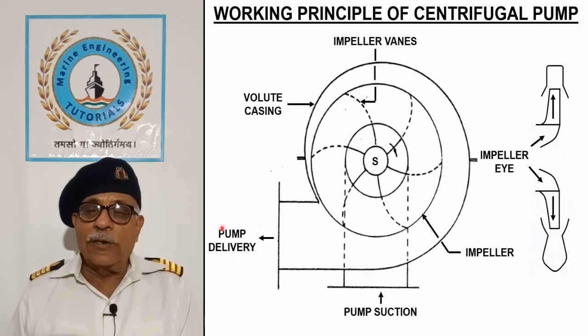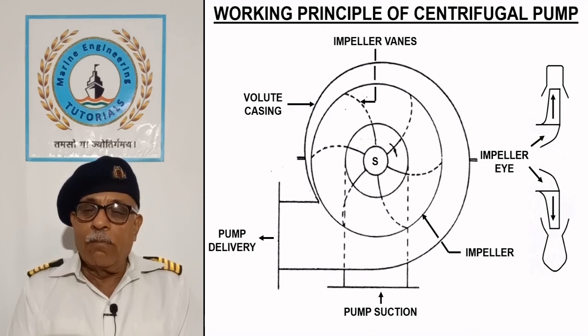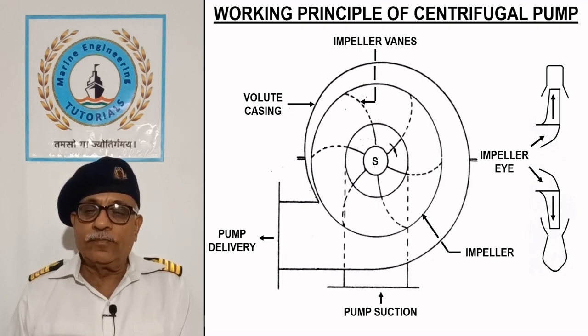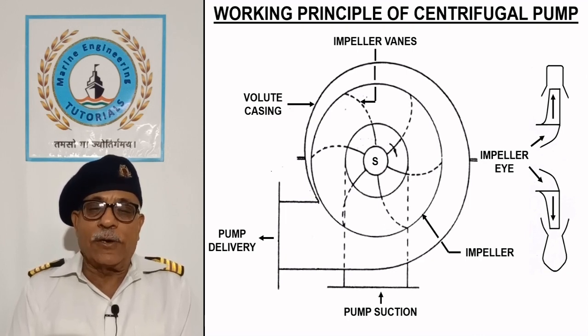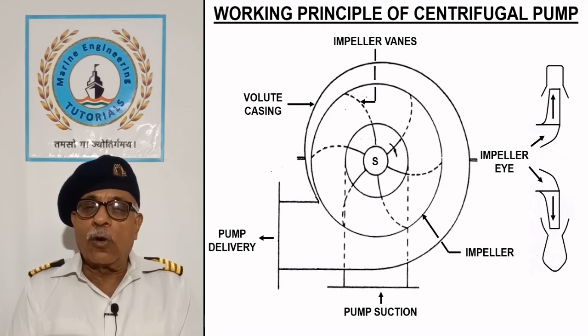The liquid is finally discharged from the pump delivery connection. A centrifugal pump provides a constant head or pressure for a certain system because the impeller diameter is fixed and the motor usually operates at constant speed. As the maximum pressure developed by a centrifugal pump is limited, it does not have a relief valve as required by displacement pumps, and it is usually started with the delivery valve closed for limiting the starting torque or motor current.